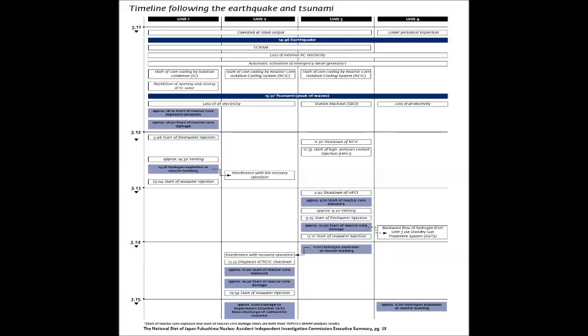In parallel, the operators were working on plans to inject low-pressure water into the reactor pressure vessel to restore water level. But first, they had to depressurize the reactor pressure vessel to below 100 pounds per square inch so the water could be injected via portable pumps. These plans were complicated by the loss of power. All valves were having to be operated manually or by the use of portable batteries in the case of motor-operated valves and portable air compressors in the case of air-operated valves.